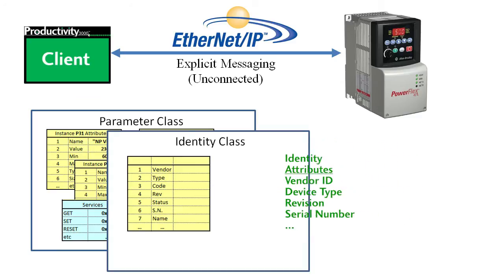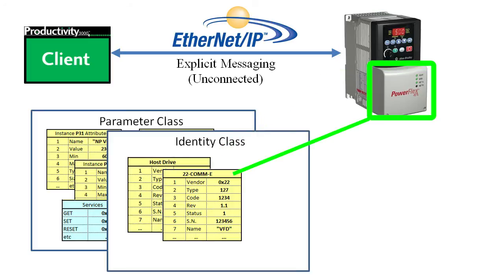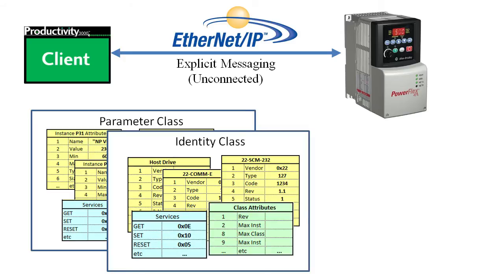Here's the predefined template of attributes for the Identity class. The vendor just fills in the blanks to create an instance for each object — here's the drive instance, here's the EtherNet/IP adapter instance, and you might have some other communications modules. The drive manufacturer will create one of these instances for every option available. Since they all use this standardized template along with a standard list of services and class attributes, anyone who wants to know about the identity of one of these objects knows how to get it.